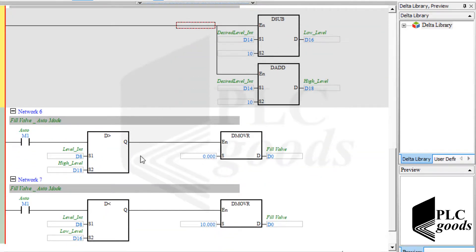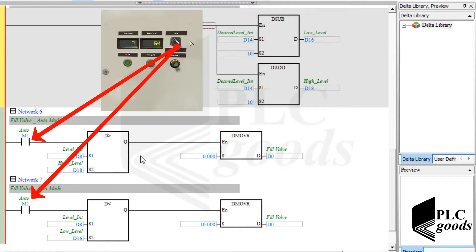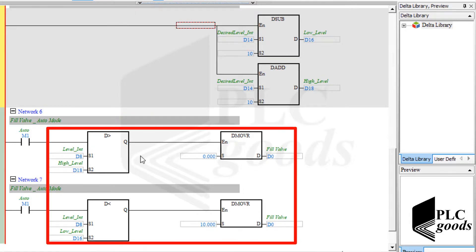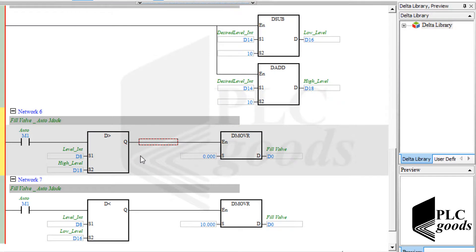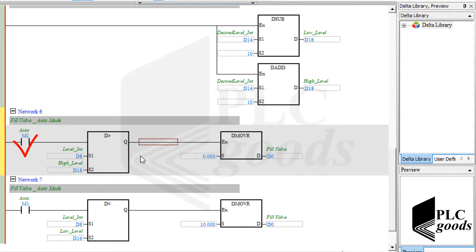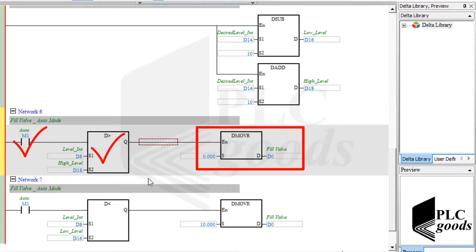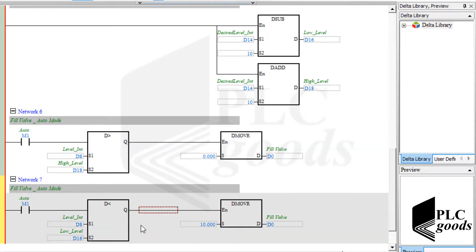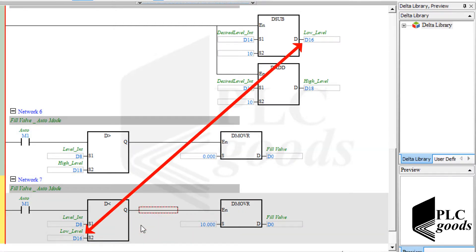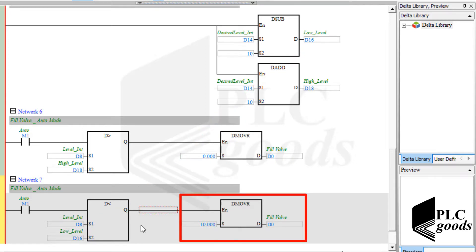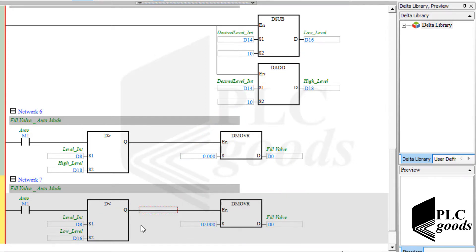If I select the auto mode, the PLC will execute these instructions. The first network compares the current level with the high level — it's only 10 centimeters more than the desired level. Therefore, if the automatic mode is selected and this condition is correct, the inlet valve will be closed automatically. Similarly, if the current level is 10 centimeters less than the desired level, the next network will open the fill valve. This was the program related to the water tank system, which has been tested before. I'll see you in the next video.